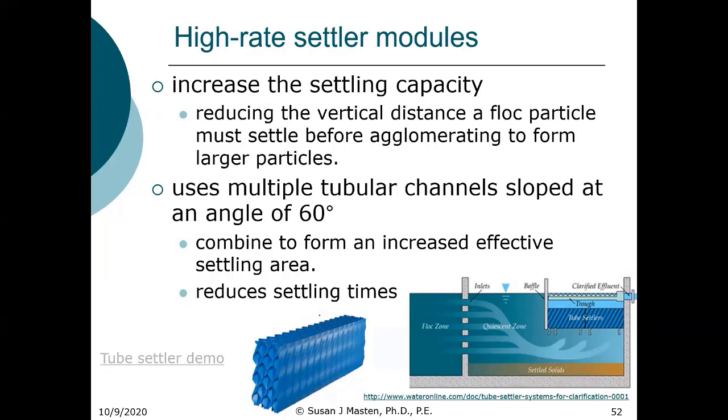So the way this works is the high rate settler, back to the high rate settler, is that a high rate settler looks like this. So it's multiple tubular channels sloped at an angle of 60 degrees. And that is used because you get increased settling. You get reduced settling times and it increases your area significantly. You can see it here. If this is the sedimentation basin here, and you add these tube settlers, you've increased the effective area by a very significant amount. I'm going to, I've got a video. It's just a short demo of a tube settler.